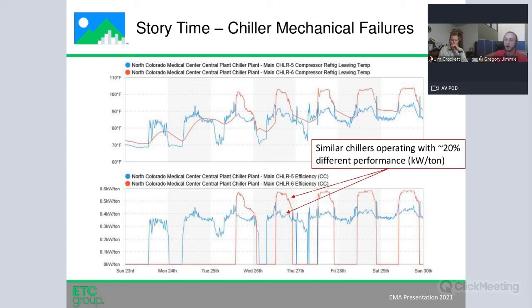So now everything's basically coated with oil, and that'll impact the ability of that heat transfer to occur. You can have a failed O-ring and have rapid refrigerant loss. So there's other failures, other mechanical problems that can happen that you may or may not notice. I would hope that a refrigerant leak is something you notice, but there's other things that are less obvious. So this is an example of one that we had found was actually a mechanical installation not done quite right.